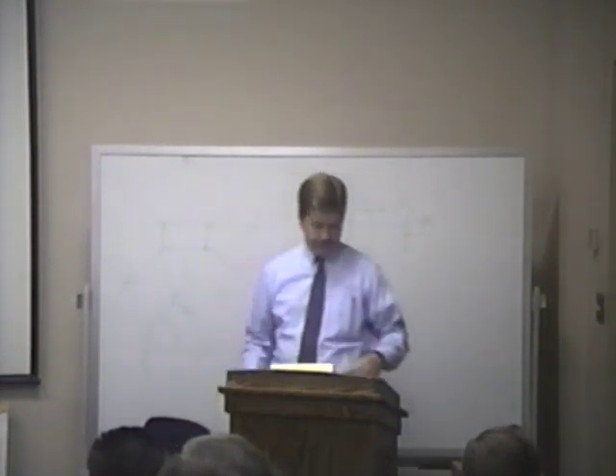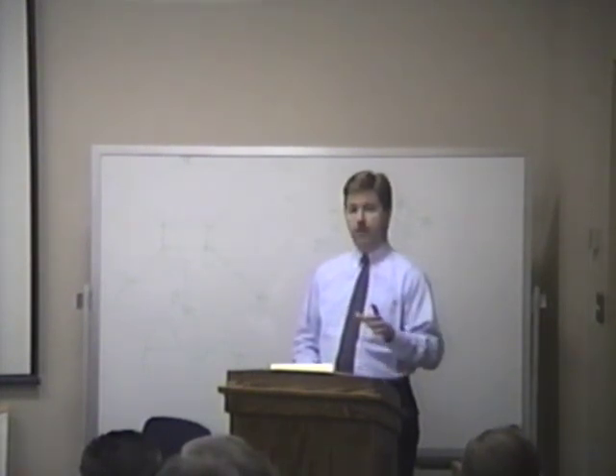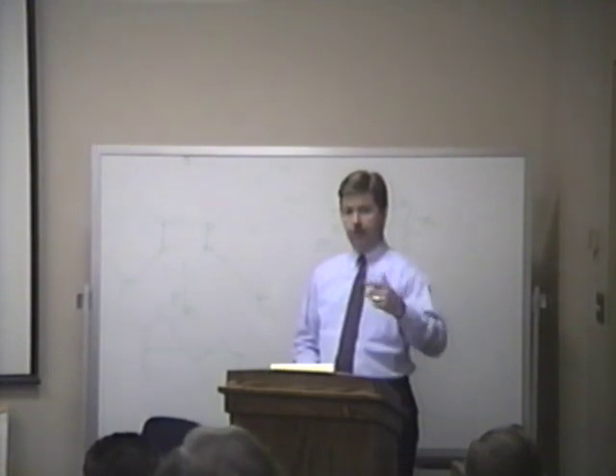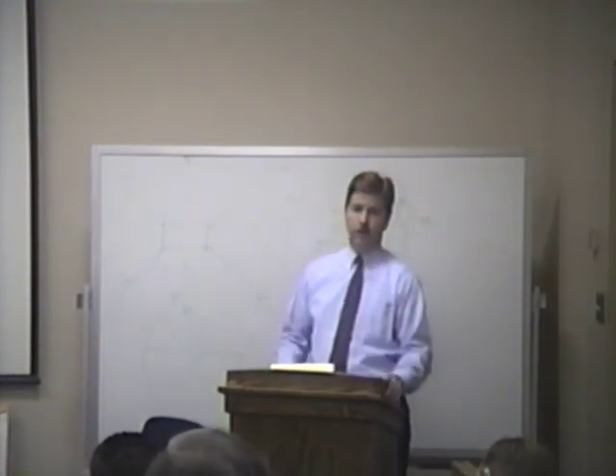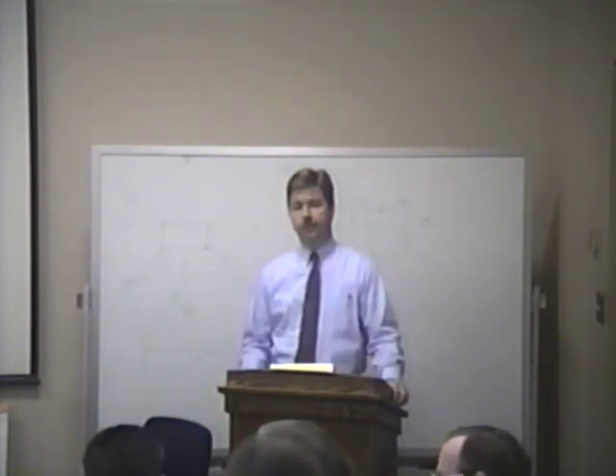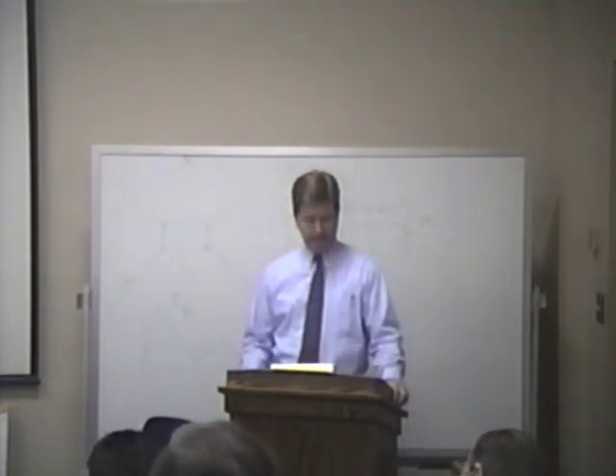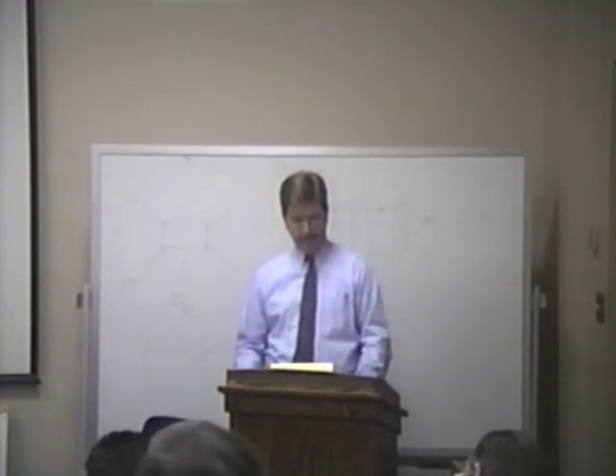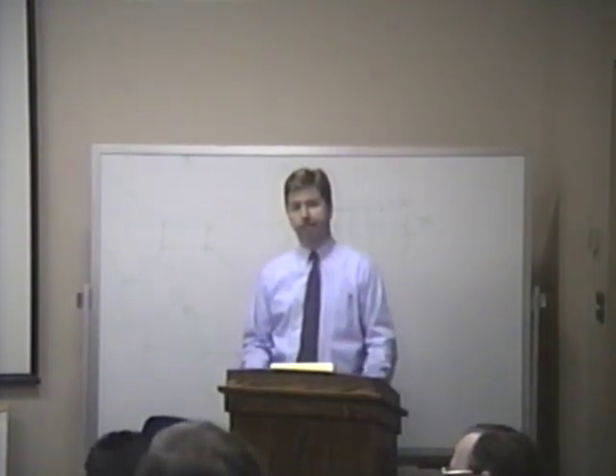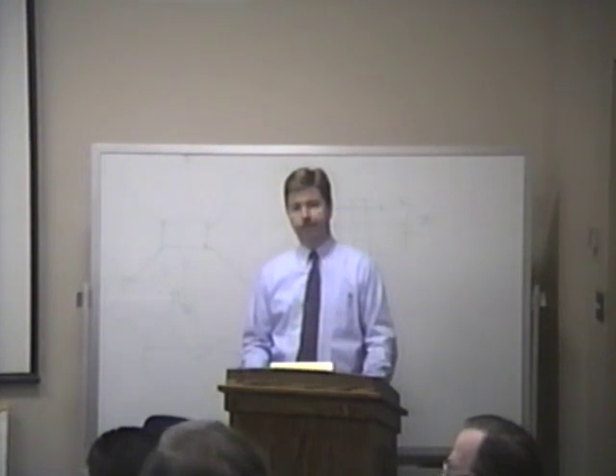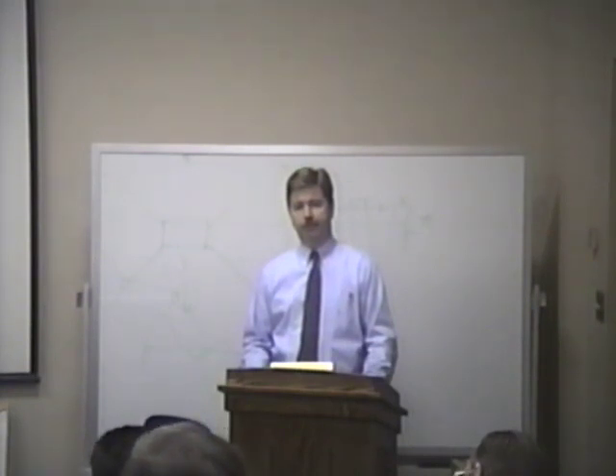I'll have Ed make this technical because it'll be better for you. The rating is how much energy it can produce for how much it takes to produce. I'll let you on your EERs and SEERs. The seasonal efficiency is discussed in here, but basically it's BTUs per watt. That's what EER is talking about and what SEER is talking about. BTUs per watt means the cooling generated divided by the amount of wattage it takes to do that. So a 6 versus a 9: a 9 would generate 9 BTUs per watt of electricity, which is 50% better than a 6.